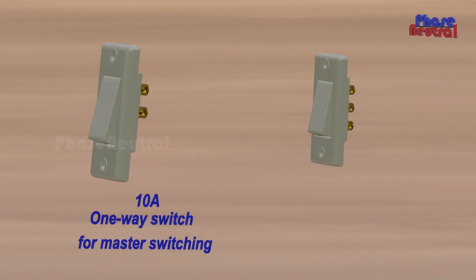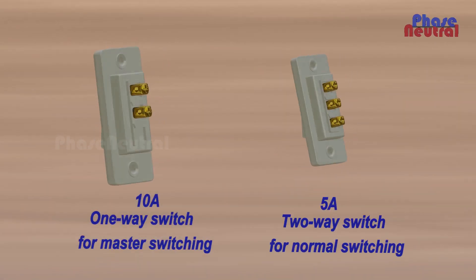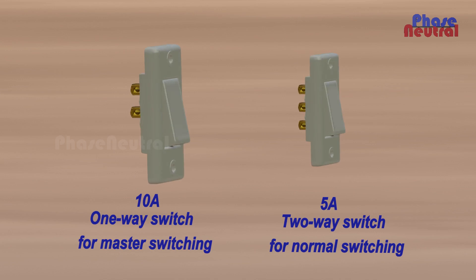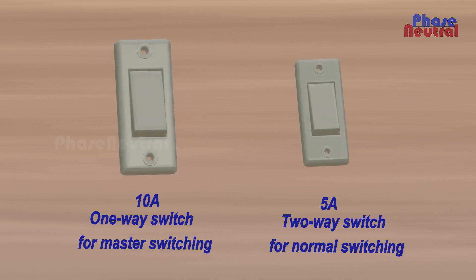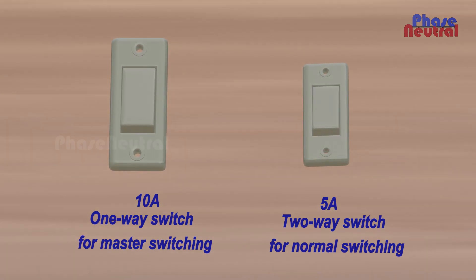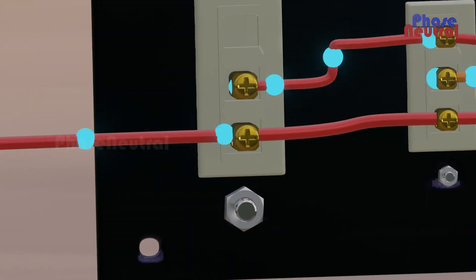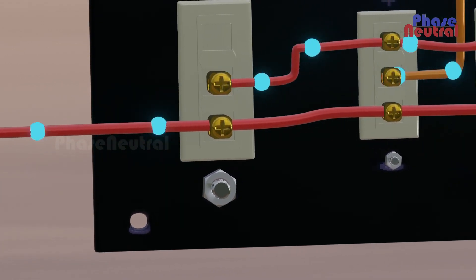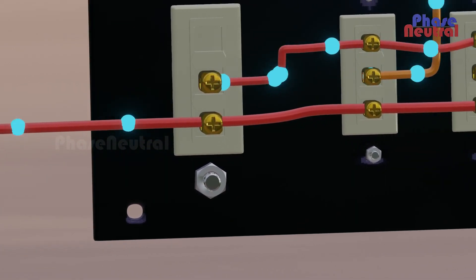You can use any one-way switch as a master switch, but its capacity should be higher than normal switches, because all light load current passes through this master switch when the master switch is in on position.